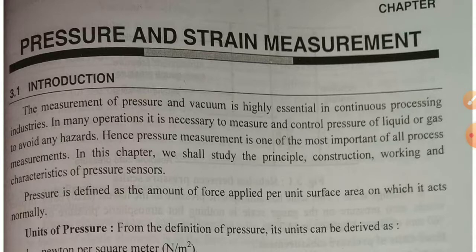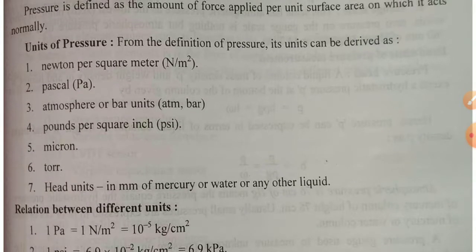Now pressure is defined as the amount of force applied per unit surface area on which it acts normally. From the definition of pressure, its unit can be derived. The units are: Newton per square meter, Pascal, atmosphere or bar, pound per square inch (psi), micron, torr, and head units in millimeter of mercury, or of water or any other liquid.